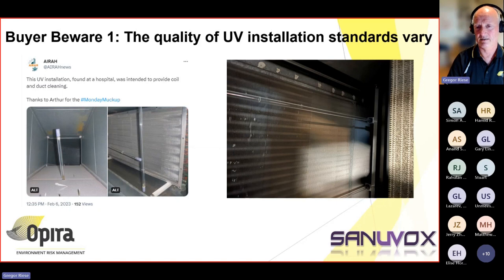That's a hospital in New South Wales, with an unshielded UV upstream of the cooling coil. Fantastic, good installation in terms of keeping the coil clean and the back of the coil remain clean. Unfortunately, those filters were destroyed - they were F8 rigid V panel filters, and they were just falling to pieces. I wasn't sure how long they'd been in there, but it's an example of probably a poor installation. So the quality of installations vary, and be careful.